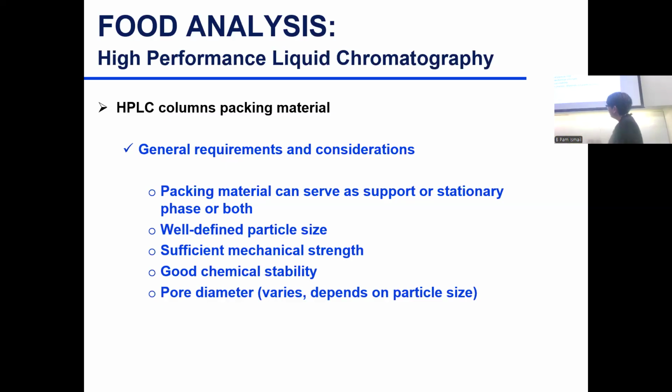Like I said, well-defined, small particle size, very good ability to pack with low void volume, and can withstand mechanical stress due to high pressure. And you don't want it to dissolve in your mobile phase. So you want chemical stability rather than chipping away your functional group with every run, or having it interact covalently with the components and then it degrades over time.